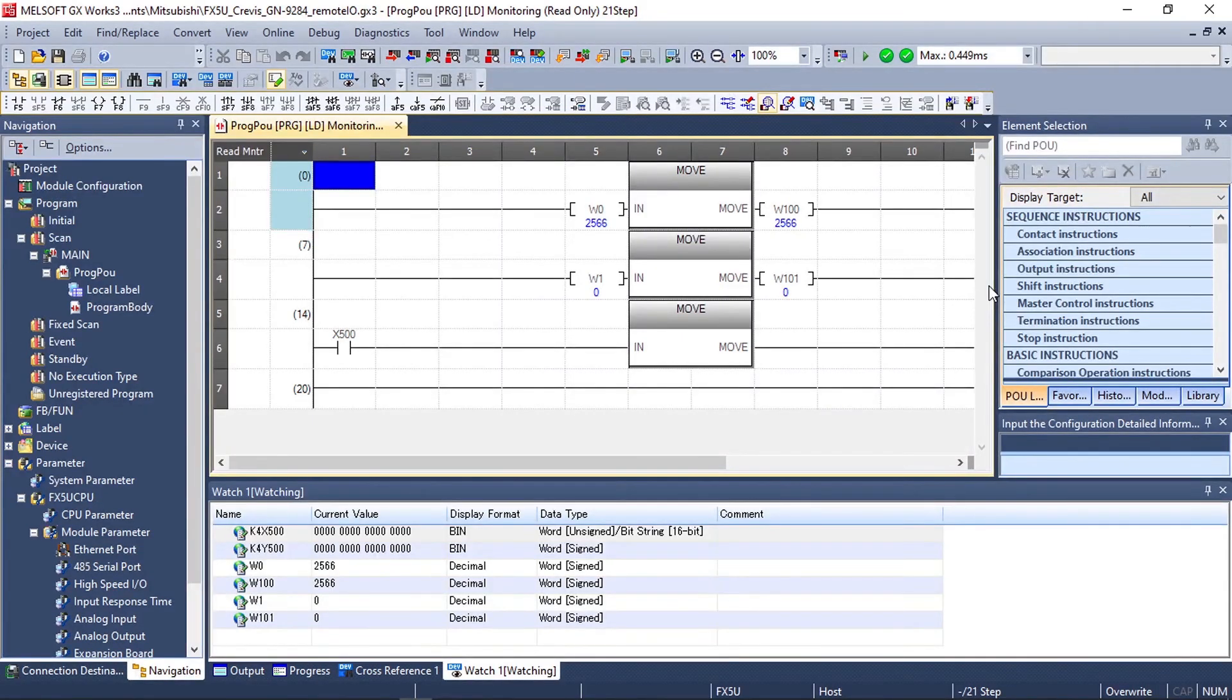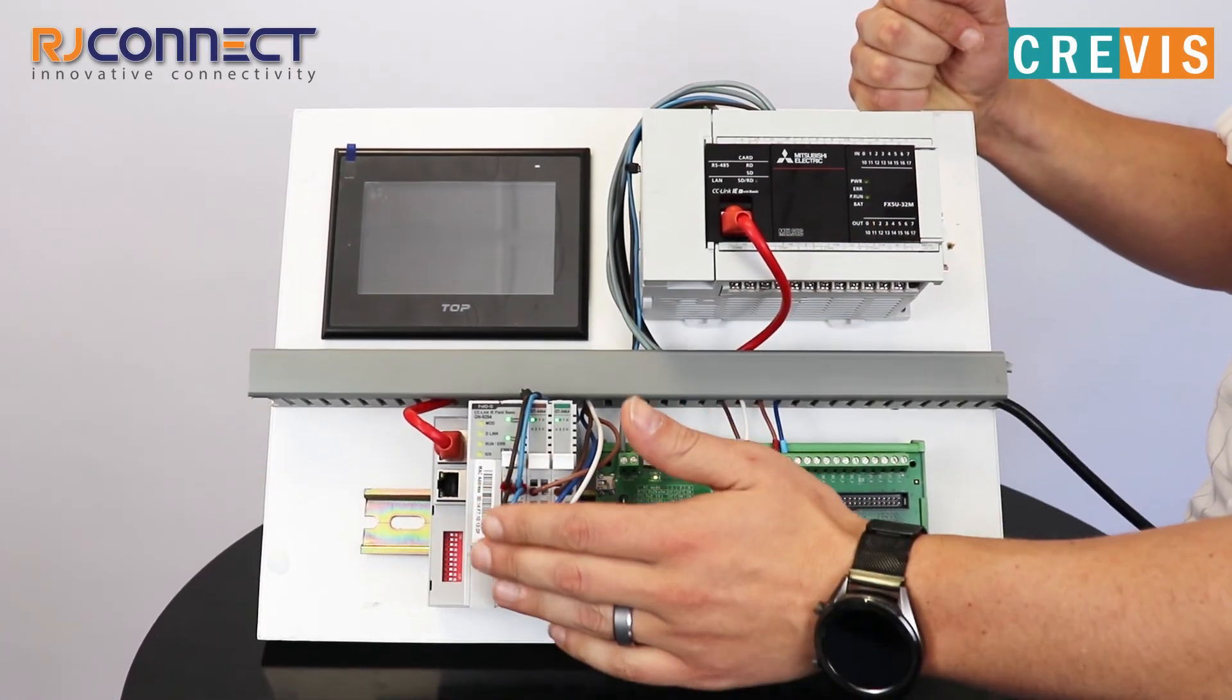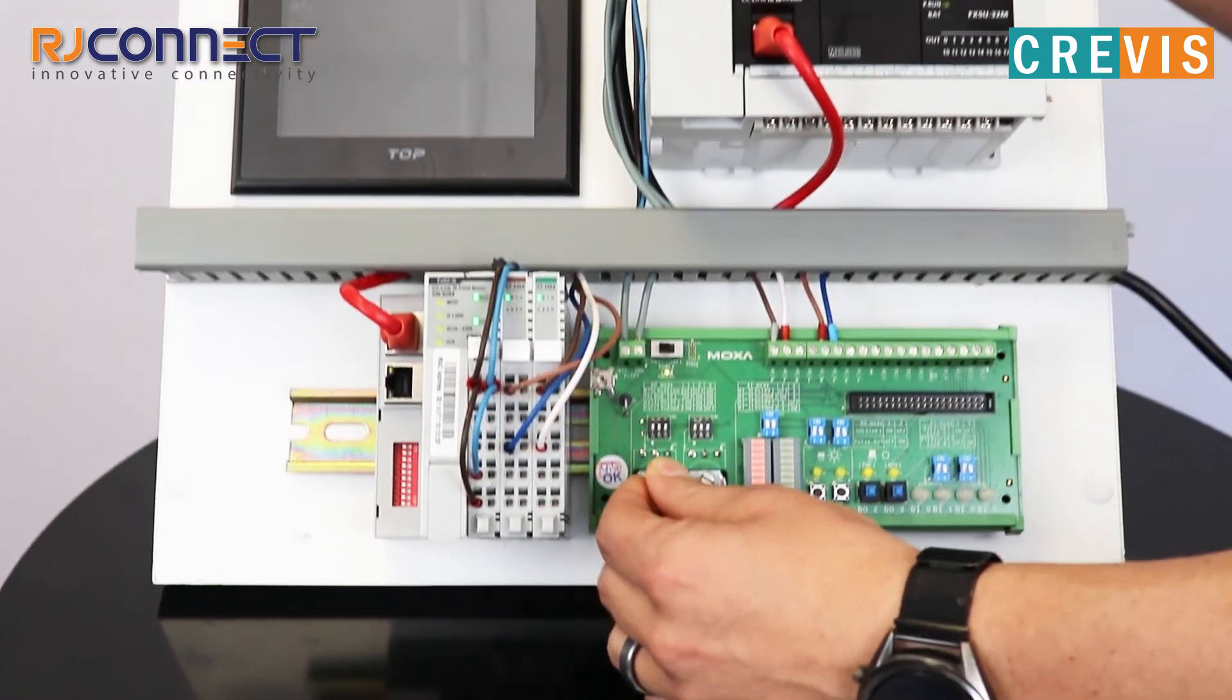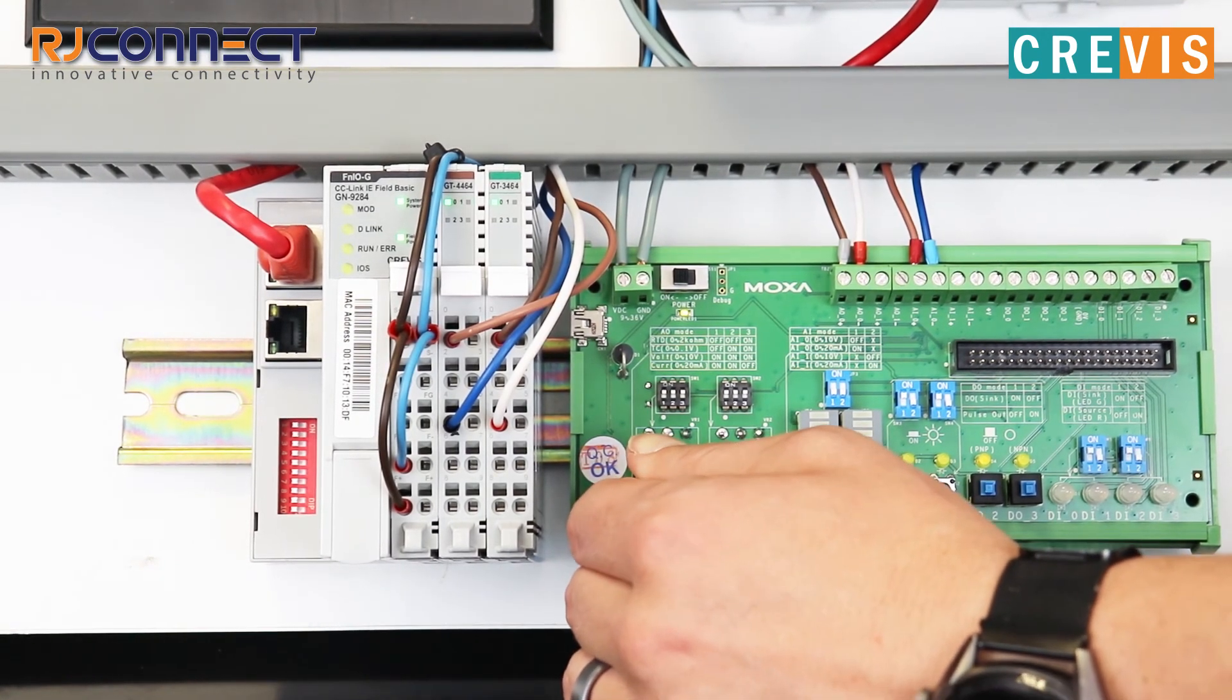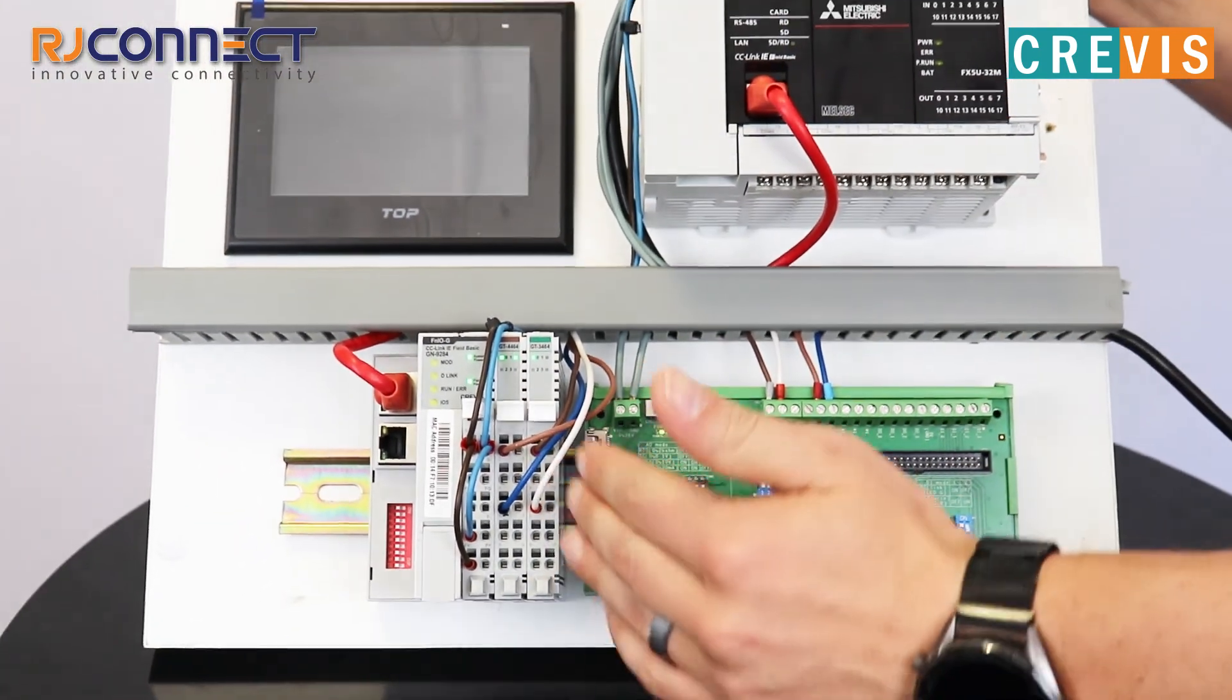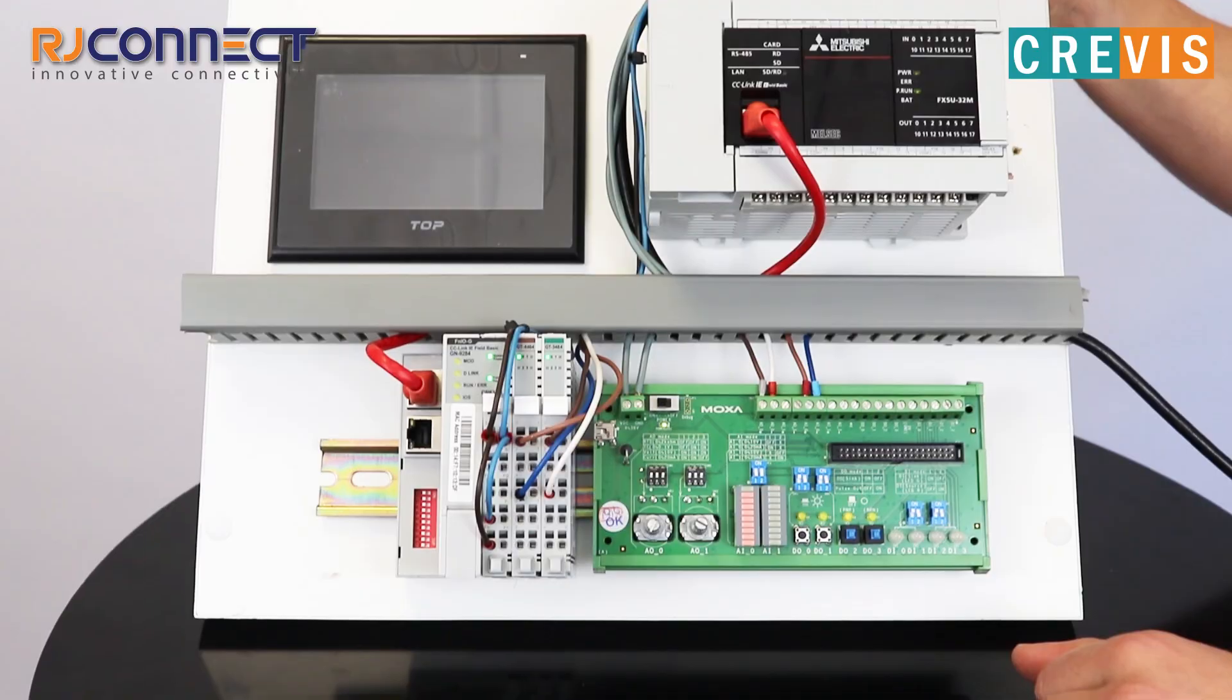Now let's look at our IO board connected to the analog input and output cards for our Crevis network adapter. After configuring our PLC to communicate with our Crevis remote IO we can now see the analog input on the analog input card pushing up our value on the analog output and there we're turning it down again. We are now reading the analog input through the PLC, processing that value, and then writing to the analog output to change the value on the LED bar.